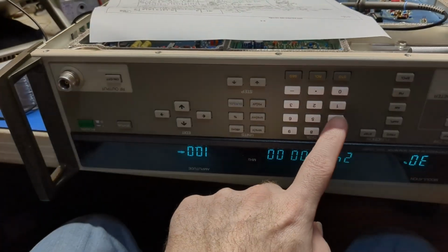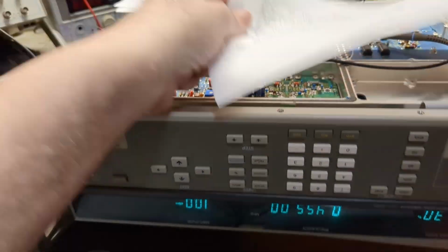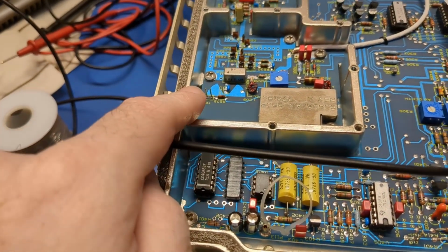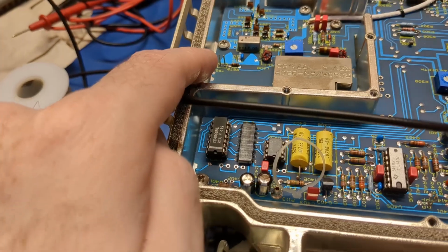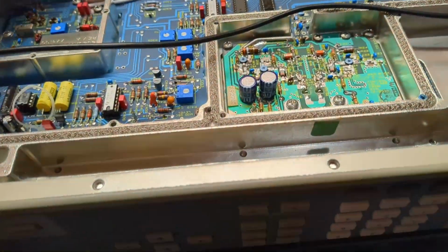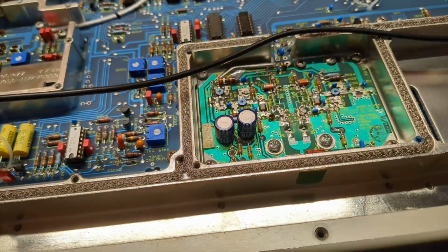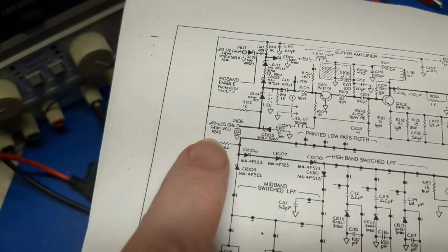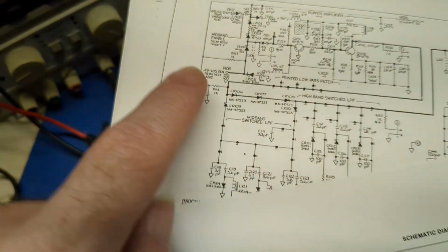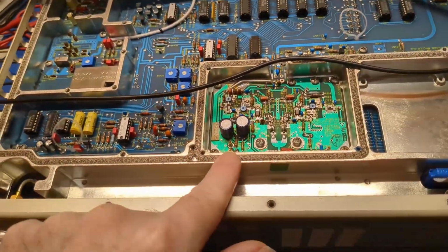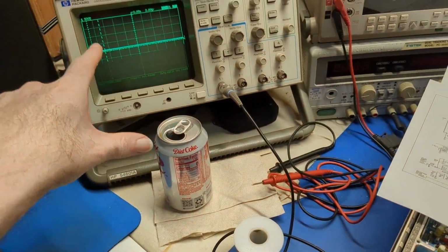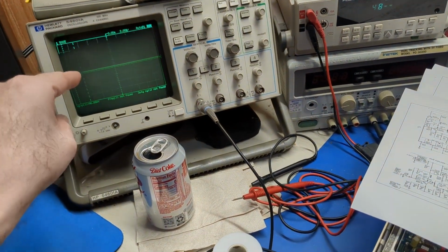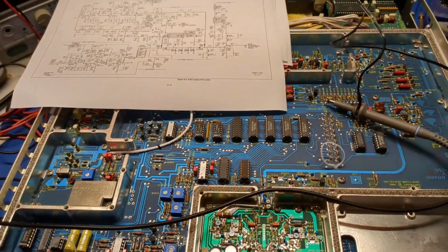But if I say 455 kilohertz, again, we are way, way, way down. But a 455 kilohertz can be detected from that. But we've got an 800 megahertz local oscillator frequency coming from the synthesizer, and then it's mixed with the frequency that comes out of this module here, which is a variable frequency oscillator, somewhere between 0.49 to 1 gigahertz, thereabouts. So that is working, because when I do get a frequency out of here, even though it's very low, it is accurate, which means the synthesizer board is functioning.